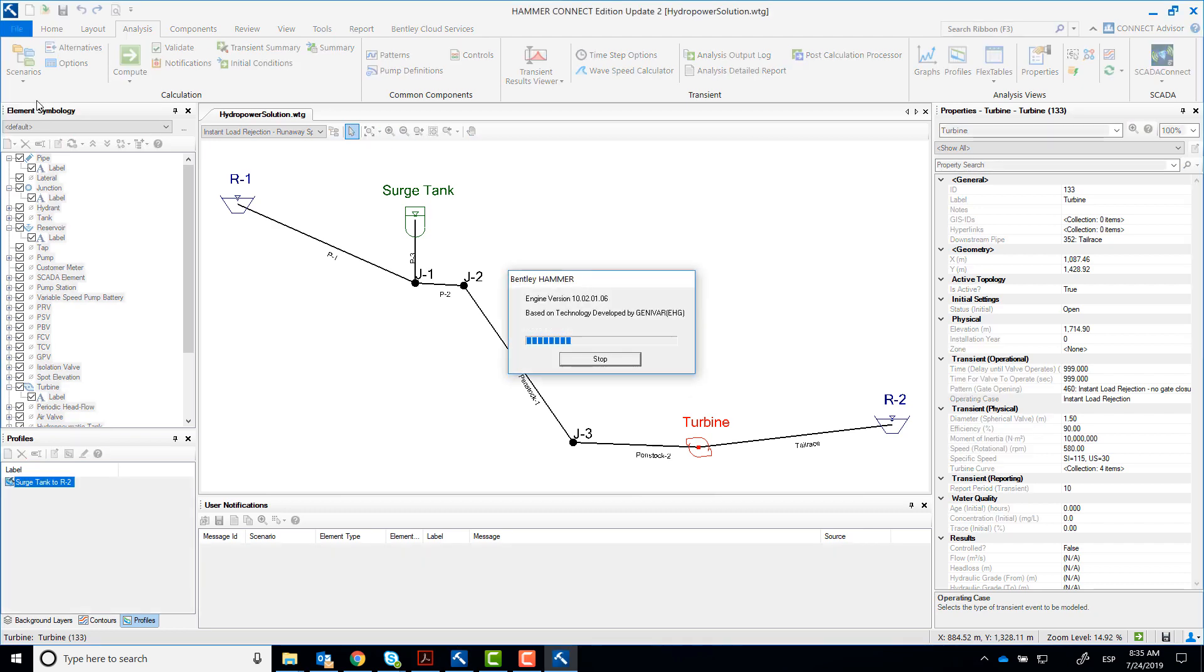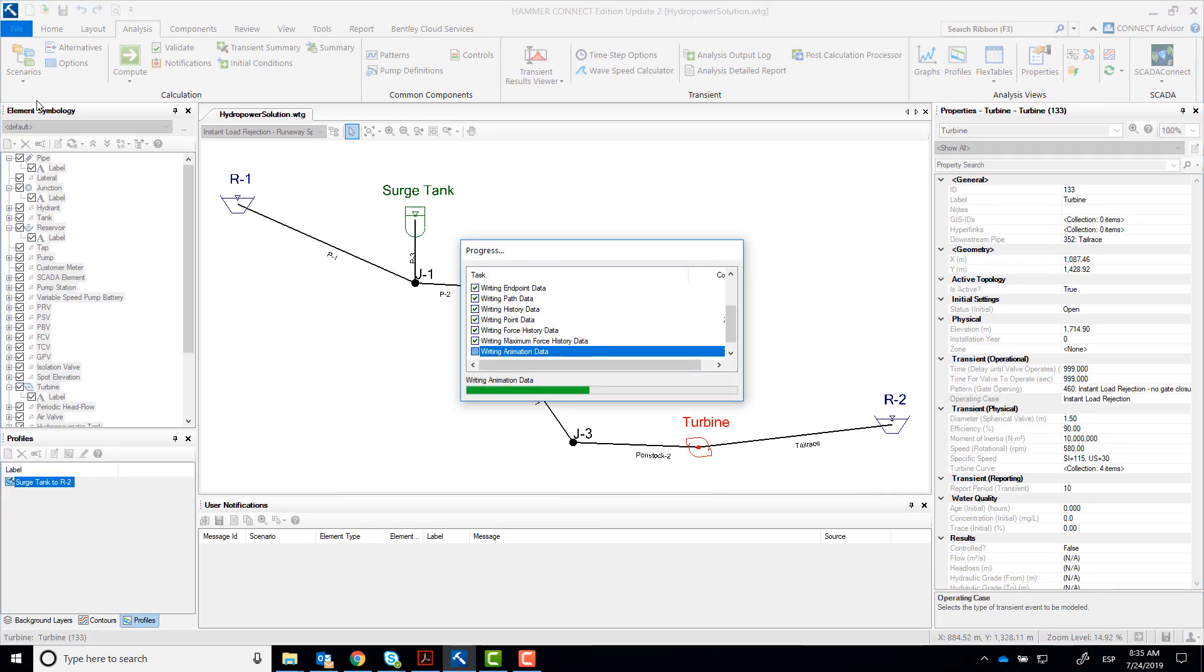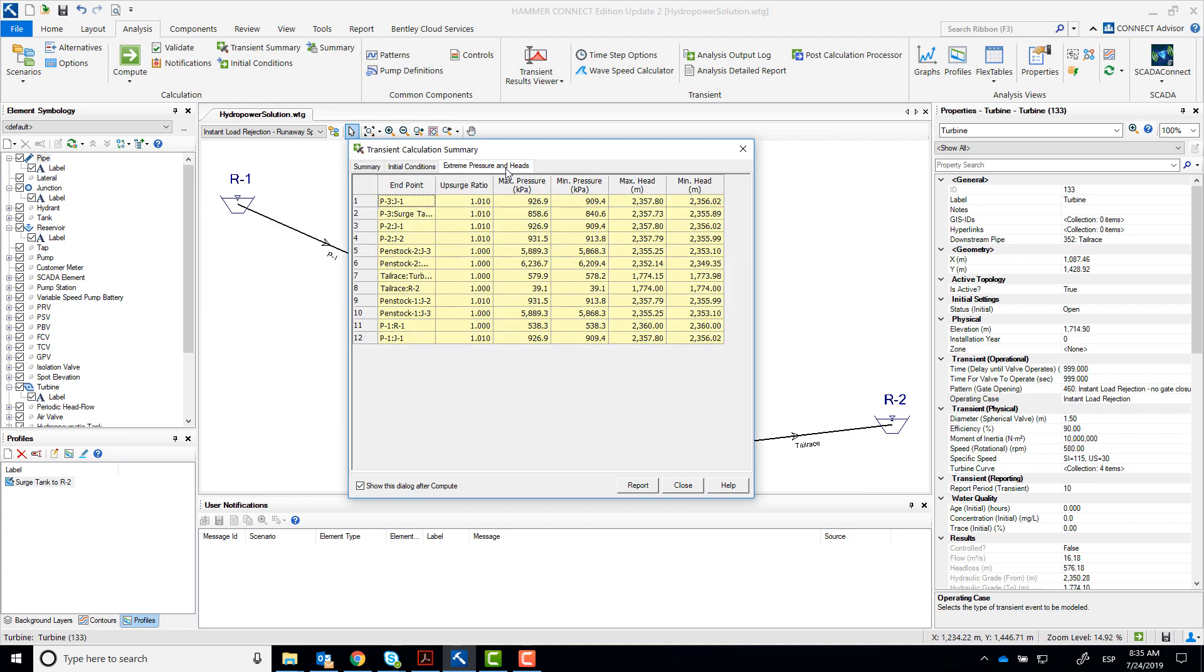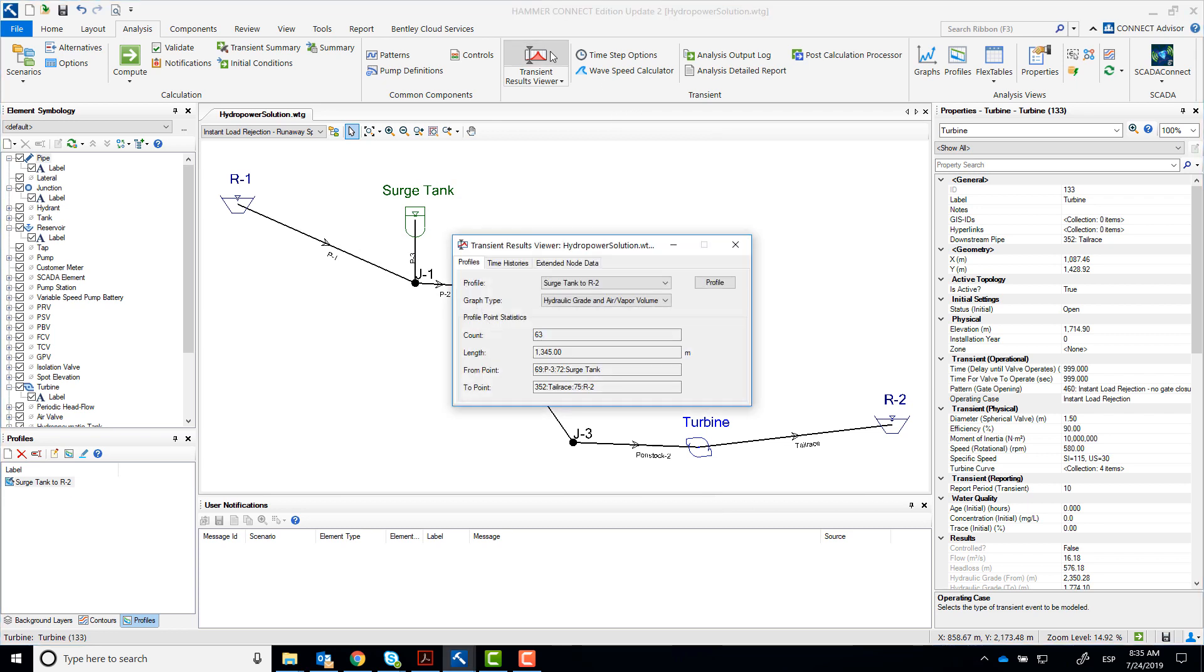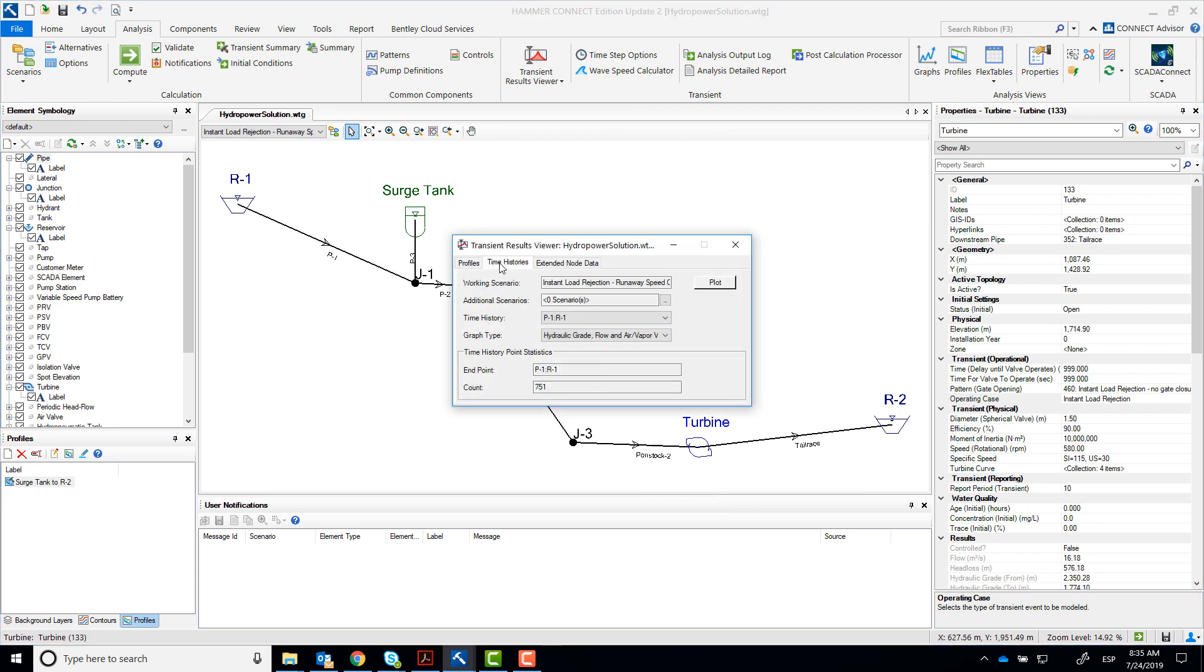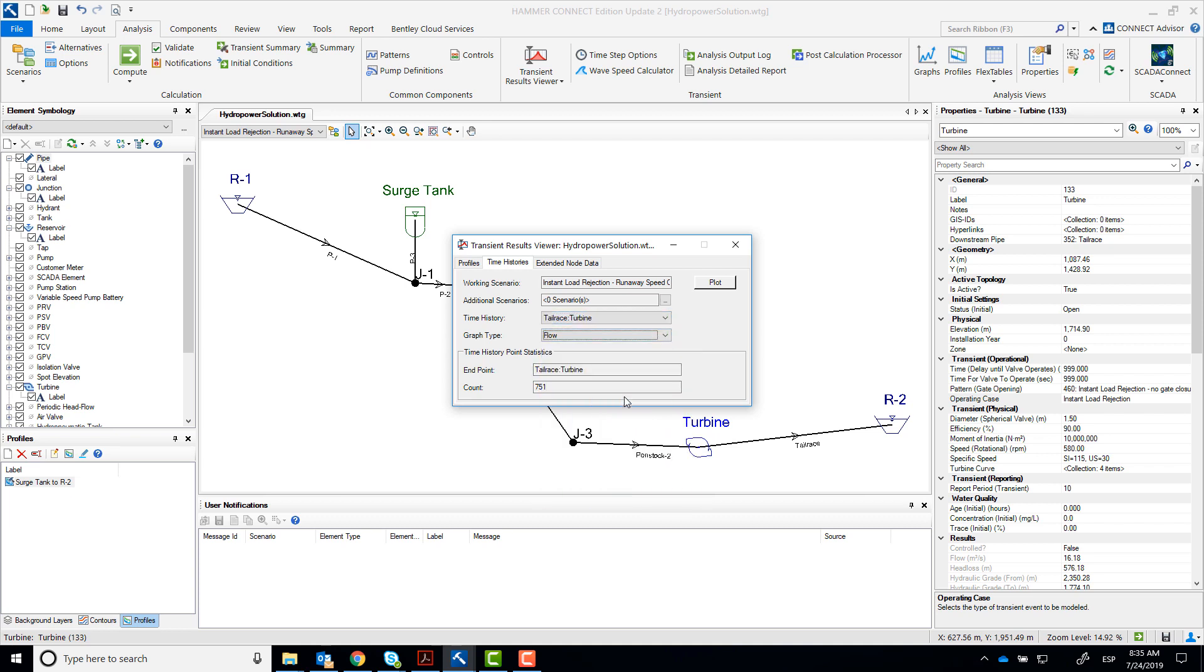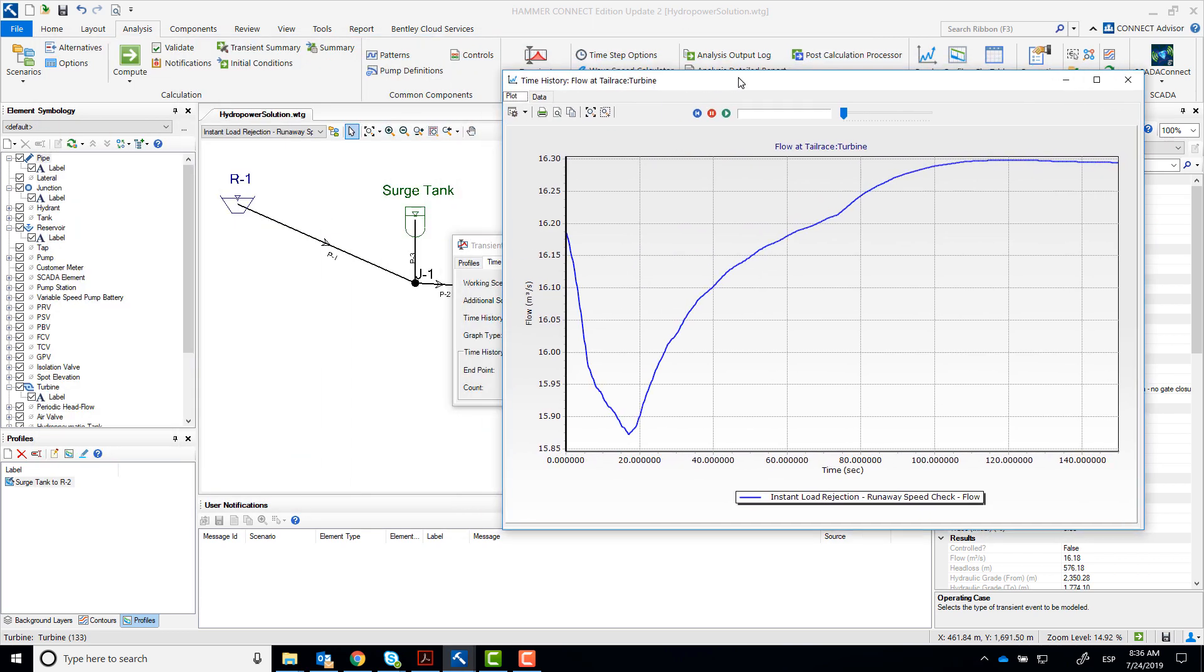Compute the scenario. And notice that there are no user notifications for this scenario since no transient was expected as the wicket gates stayed open. Go to Time Histories and take a look at what's happening near the turbine. When the speed increases as the electrical load is rejected, there is a change in the efficiency of the unit leading to choking, a decrease of the flow as you can see in this graph.